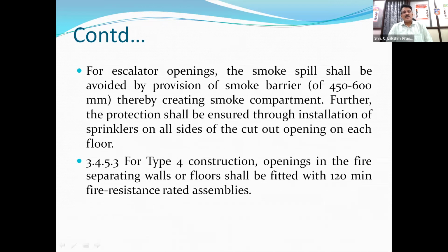Then, for escalator openings, smoke spill shall be avoided, with provision of smoke barriers of 450 to 600 mm, thereby creating smoke compartments. Further, the protection shall be ensured through installation of sprinklers on all sides of the cutout openings on each floor. See, in modern buildings we are providing glass facades and other front cutouts, and there is a gap between the floor and this cutout, and this acts as a channel for spreading of smoke in case of fire in the lower floors. So this has to be properly protected with a sprinkler system and also fire stops. That is very important. It is very clearly mentioned in Part 4 of the NBC. For Type 4 construction, openings in the fire separating walls or floors shall be fitted with 120-minute fire resistant rated assemblies.